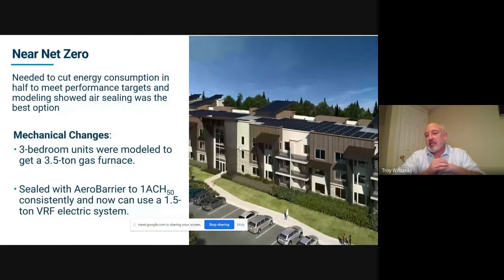One thing I really like to point out is the impact on the mechanicals. Through energy modeling, their 3-bedroom units needed a 3.5 ton gas furnace—that's what was originally required. Once we guaranteed them 1 air change and did the value engineering exercise, that turned into a 1.5 ton VRF electric system. It also enabled them to shrink the ductwork and vents, change out their insulation package, and qualify for a lot of financial incentives.